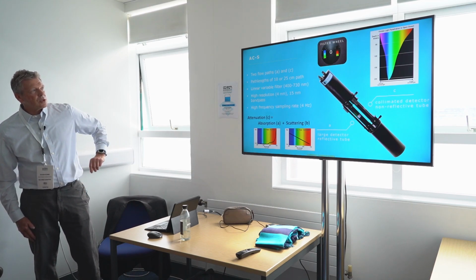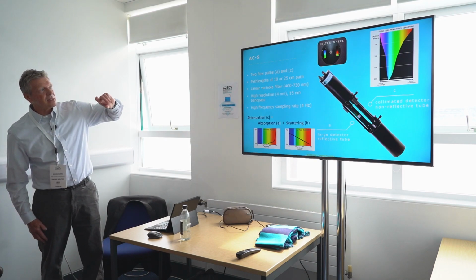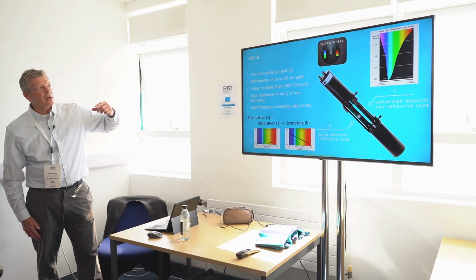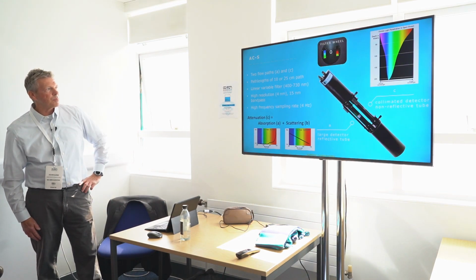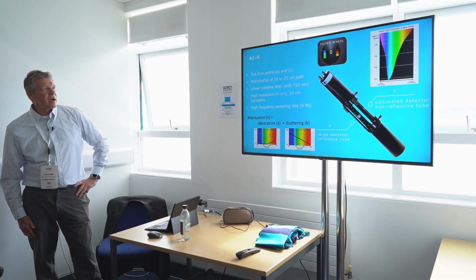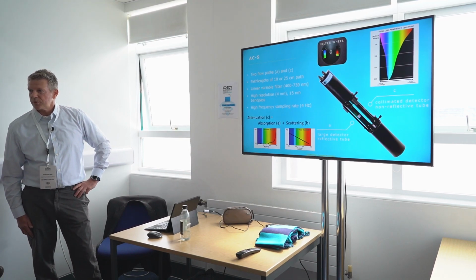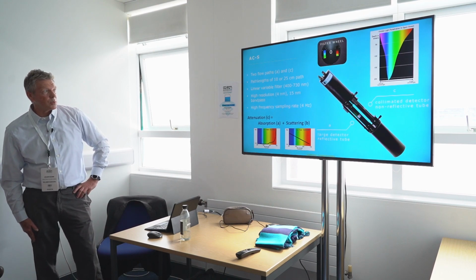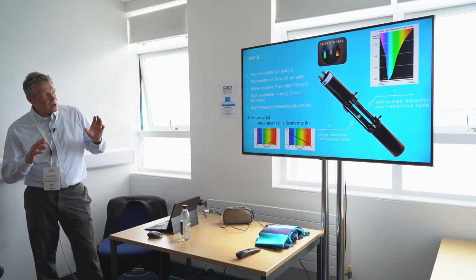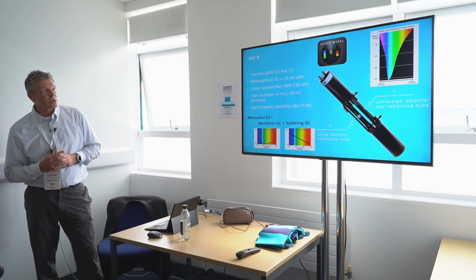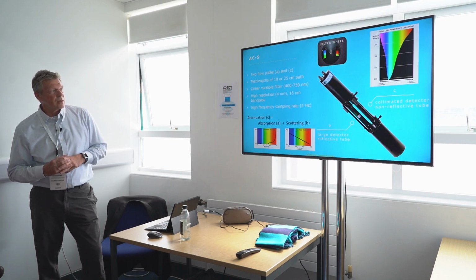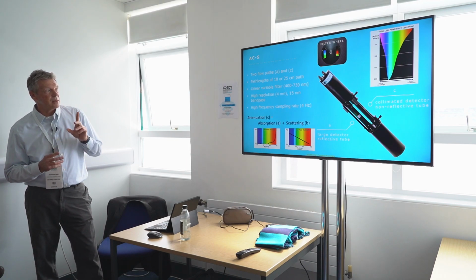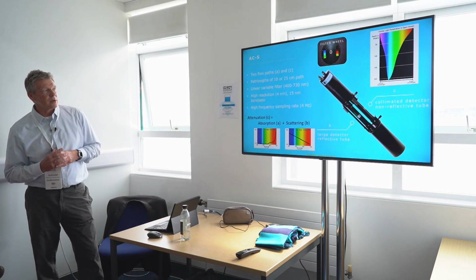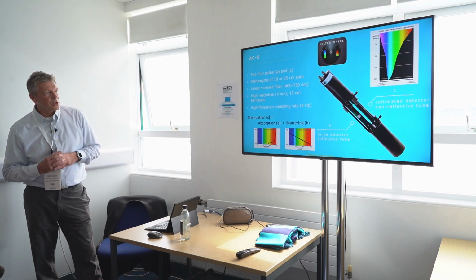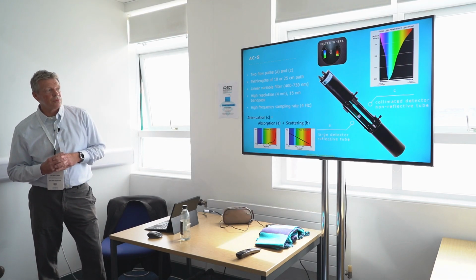The instrument consists of an incandescent light source that is run through a linear filter wheel that rotates in the system. You can get it in 2 different path lengths, 10 and 25 centimeters, depending on your application and the level of constituents you anticipate in the area you're working in. That linear variable filter covers the whole visible range from 400 to 730 nanometers with a bandpass resolution of about 4 nanometers peak. You can do very high frequency sampling at 4 hertz with this.